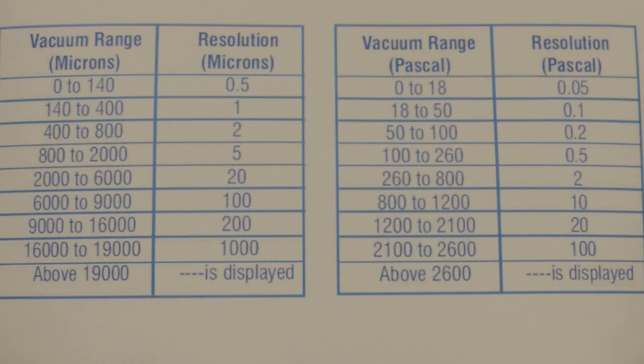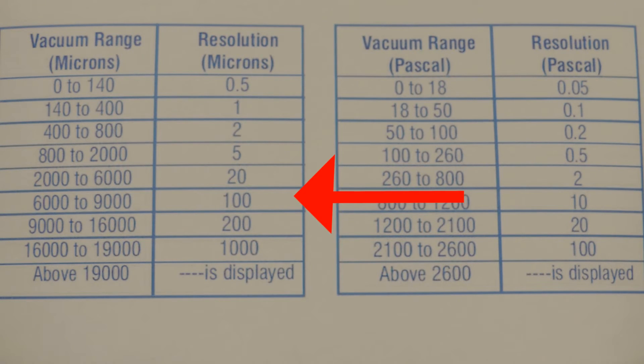The chart showing the resolution indicates, in a specific vacuum range, how much the display will change each time the display is updated. In the chart, look at the 6000 to 9000 micron range and you will see in the resolution column 100 microns.